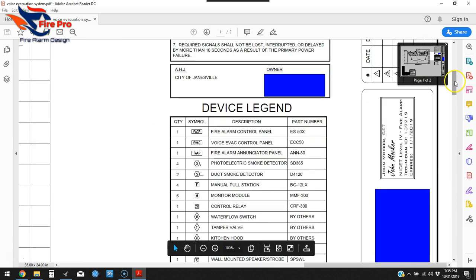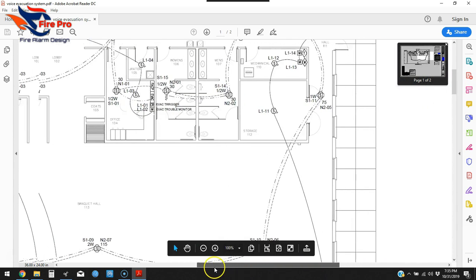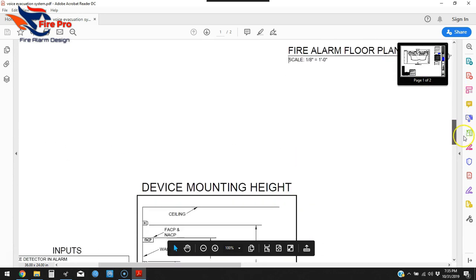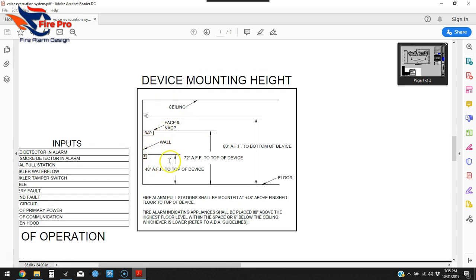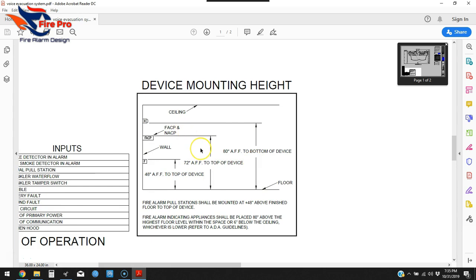Number nine is mounting height elevations for wall-mounted devices and appliances. This is a big one. Your company will likely have a standard mounting heights sheet — if not, make one. It shows typical and required mounting heights, minimum and maximum, for each device on the system: panel, pull station, wall-mount horn strobe, and annunciator.